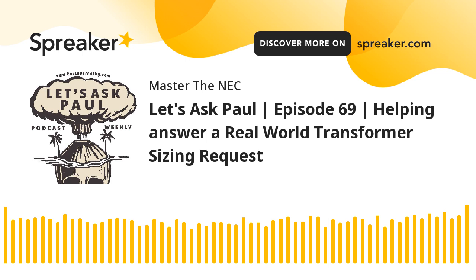This is exam prep. It's not all I do is exam prep, folks. Okay. So 831. So now let's do our math and find out what our current is for the primary side, or the capability of this for this 30 kVA transformer. So I'm going to take the 30,000. Remember, the kVA doesn't change whether you're working primary or secondary. 30,000, I'm going to divide that by 831, and that is 36.10.